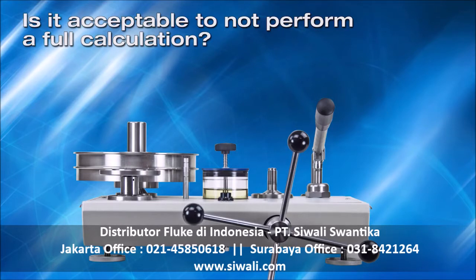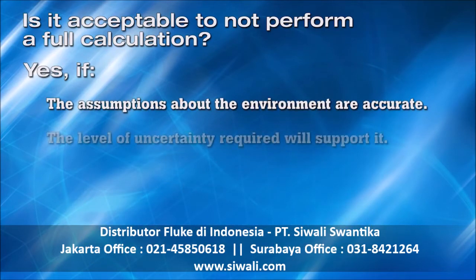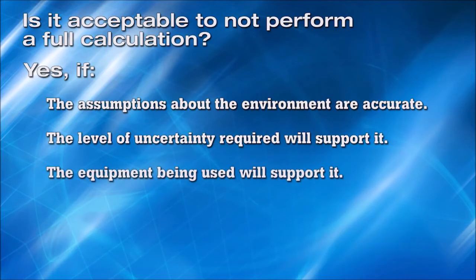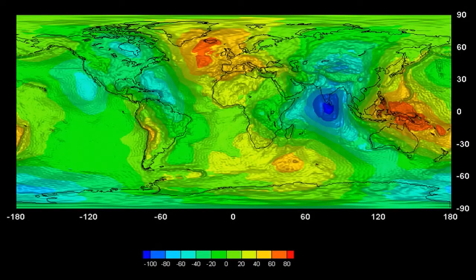The question becomes: is it ever acceptable to use a pressure balance in this fashion? Sure, it's quick, but is it right? The answer is yes, if the assumptions about the environment are accurate, the level of uncertainty required will support it, and the equipment being used will support it. As stated before, there are a number of factors that impact the pressure being generated. Perhaps the biggest is the local acceleration of gravity. Pressure is defined as force divided by area, and with a pressure balance, the force is generated by the masses being accelerated downwards by gravity.